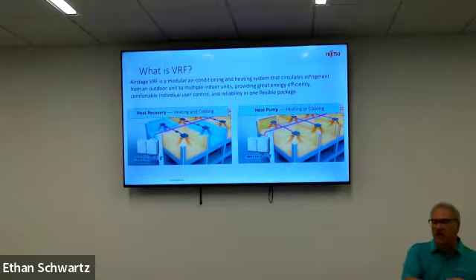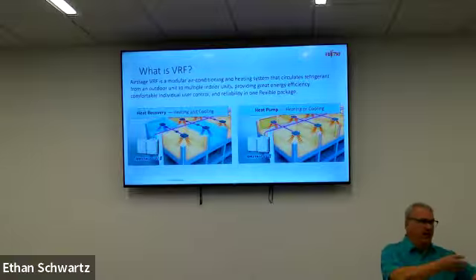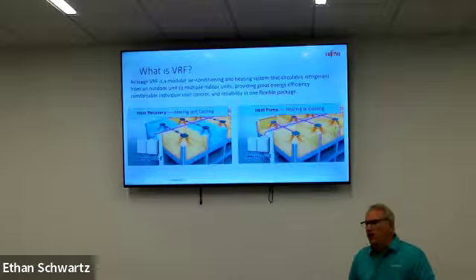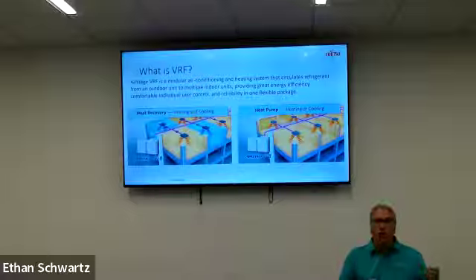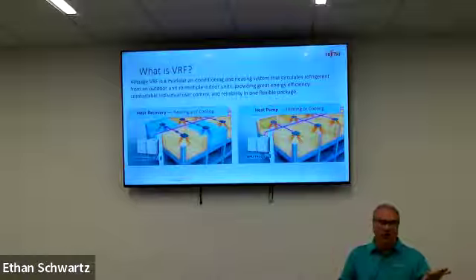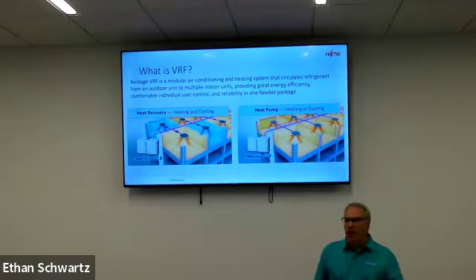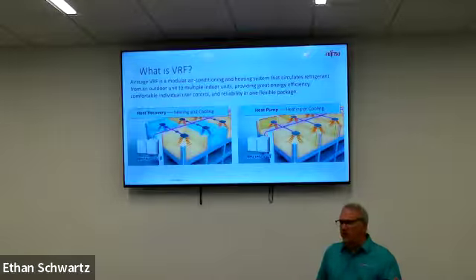because when the customer said VRF, and they said they liked this system, the question was never asked or investigated: do you want heat recovery VRF or heat pump VRF? What got installed was heat pump VRF, all in heating or all in cooling. You're going to be either calling for the compressors to run and take the refrigerant, or you're just going to be circulating the fan. So they had to add boxes, add a third pipe, take out the other outdoor units, replace them with heat recovery units, and the owner got what they wanted.